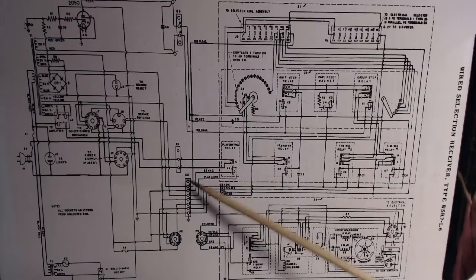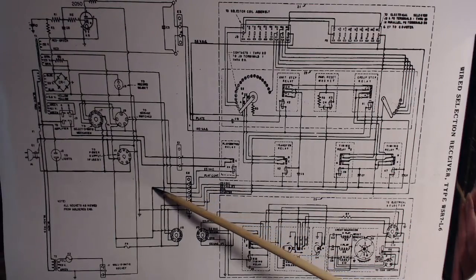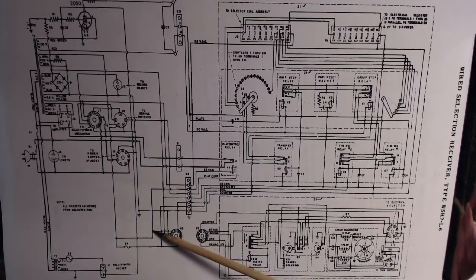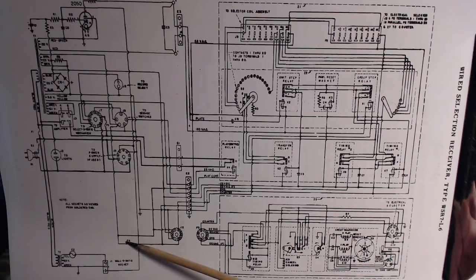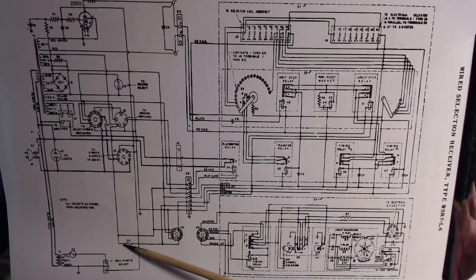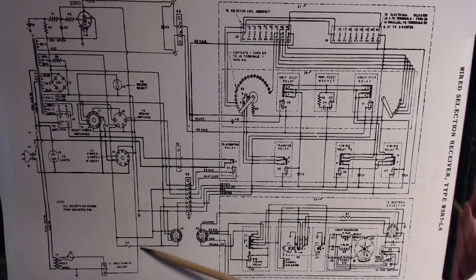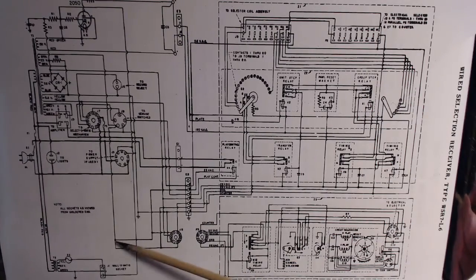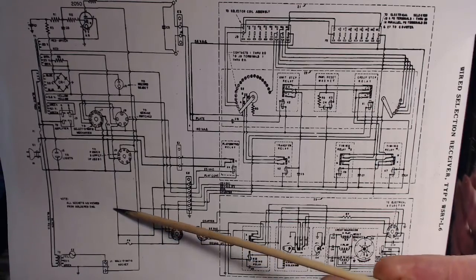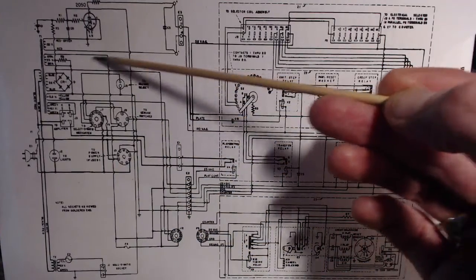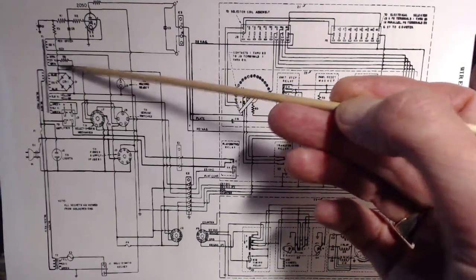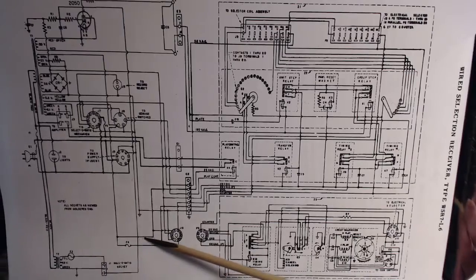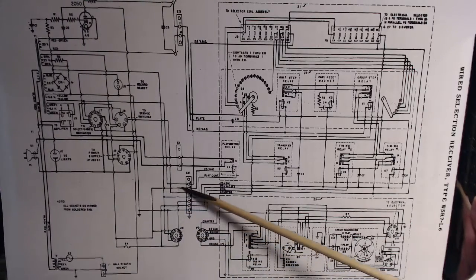So the burned wire, this is one of them. Remember one wire went to the top of a fuse holder or onto a fuse. There it is. But look which side of the fuse it's on. It's not on the downstream side. It's actually connected. Let's follow this all the way up through here to this 25 volt transformer here. No fuse.